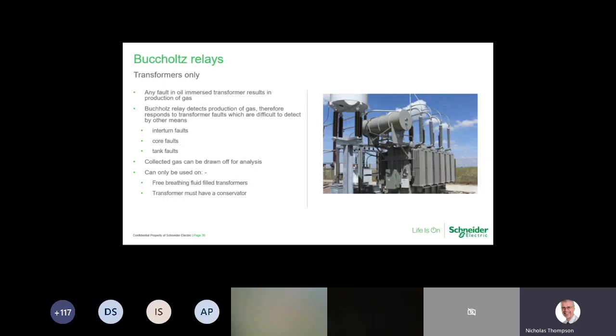Now, they are very widely used on larger transformers. You don't generally see them on distribution transformers. In fact, it's quite rare to see them below a 2 MVA transformer size. But again, it's down to what the customer prefers. So some customers, irrespective of the transformer size, will have a Buchholz on it. Now, with the Buchholz, the transformer has to be fluid filled, it can only be free breathing, and it has to have a conservator. Those are the non-negotiables.